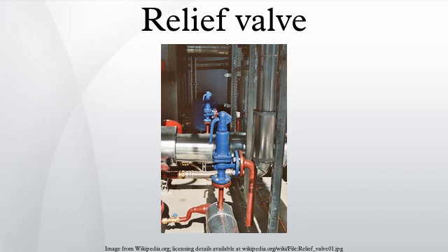Snap acting, the opposite of modulating, refers to a valve that pops open. It snaps into full lift in milliseconds. Usually accomplished with a skirt on the disc so that the fluid passing the seat suddenly affects a larger area and creates more lifting force. Modulating: opens in proportion to the overpressure.